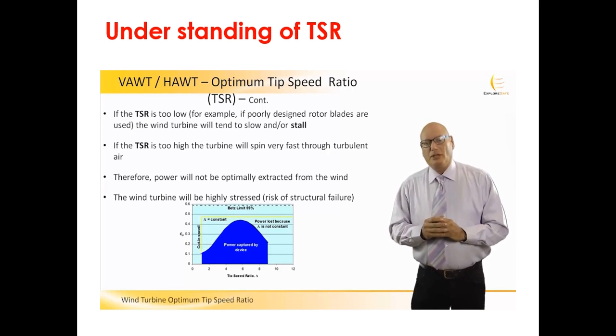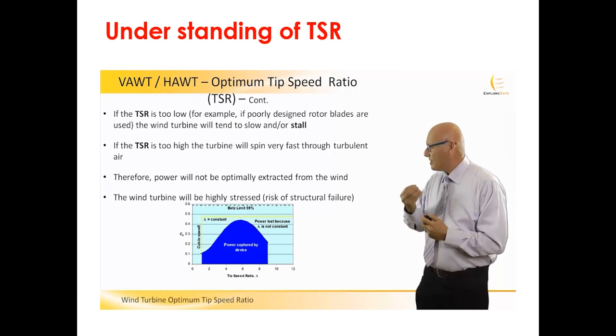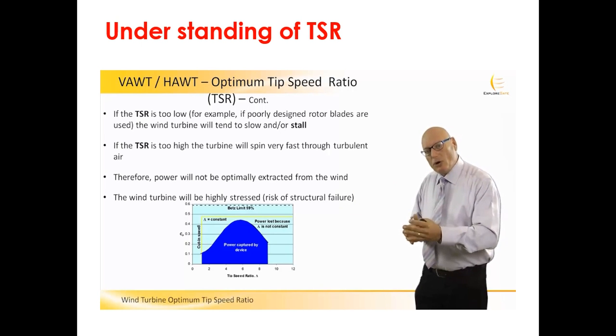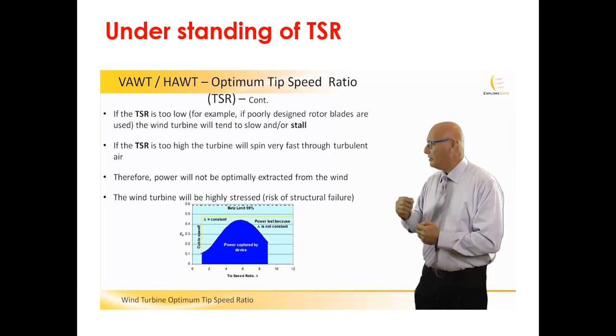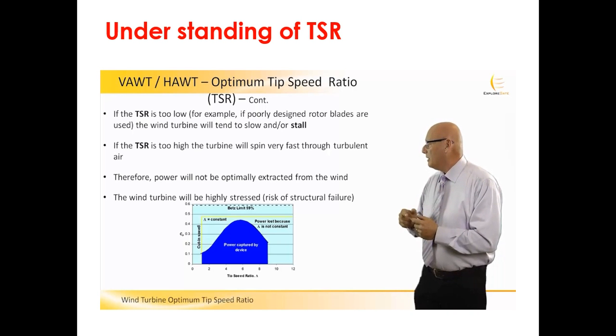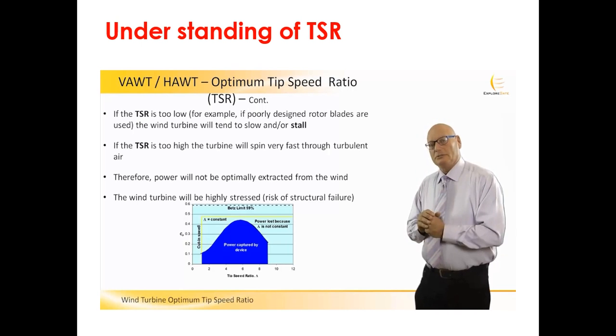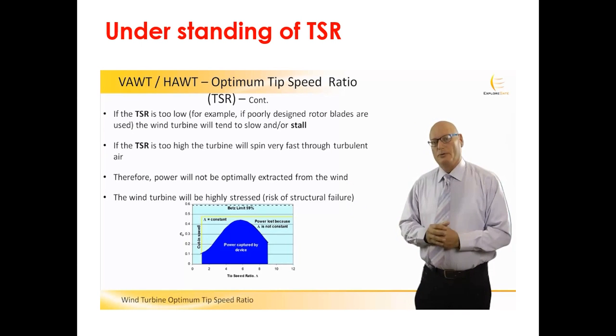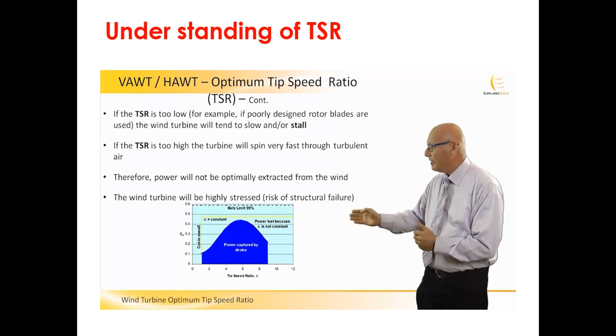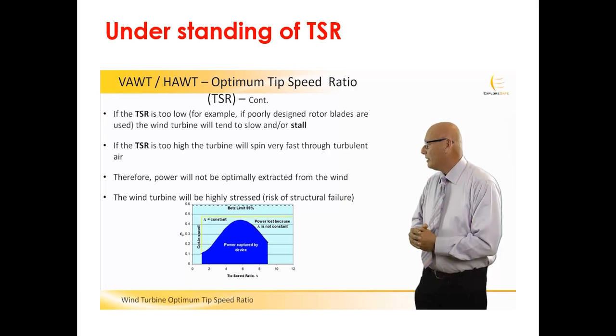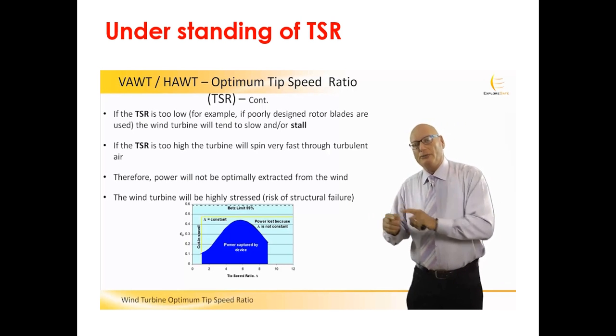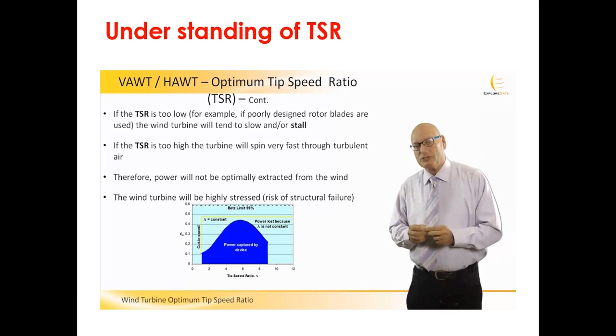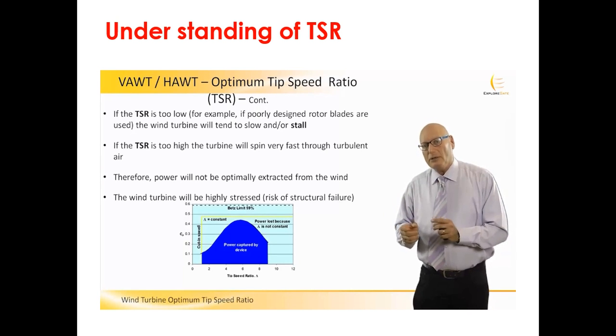Looking at the CP versus TSR graph: if TSR is too low — for example, due to poor design — the wind turbine will tend to slow or even stall, placing it on the left of the graph below cut-in speed. If TSR is too high, the turbine spins very quickly, the wind sees a solid wall, efficiency drops, and we are on the right-hand side of the graph. Additionally, too high a rotation speed causes mechanical stresses and risk of structural failure.